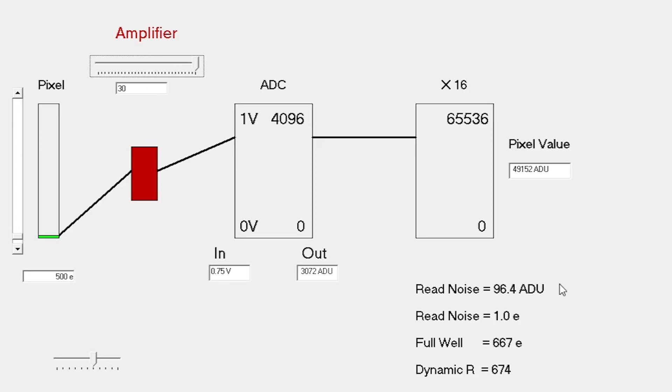The question might be, why don't we just use high gain all the time? Because it will give us the best signal-to-noise ratios. Well, that really boils down to the fact that at high gains, we have these very small usable full well depths. At a gain of 30, the full well depth is only 600 or so electrons.